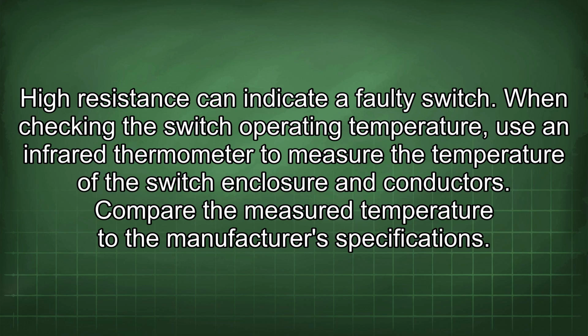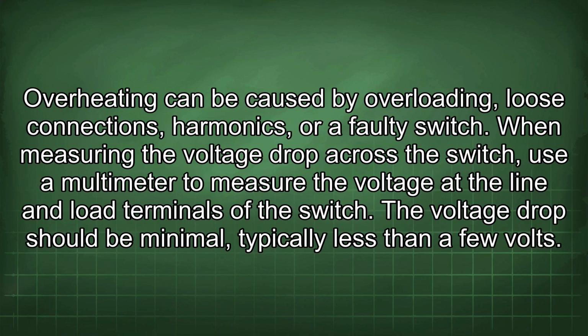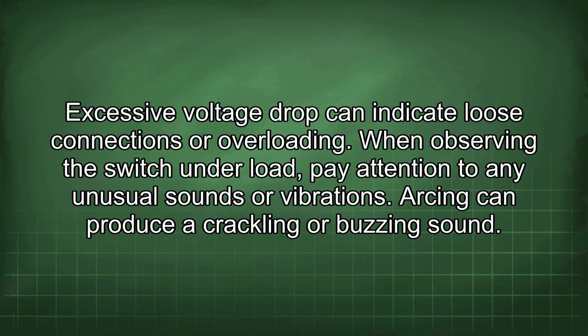When checking the switch operating temperature, use an infrared thermometer to measure the temperature of the switch enclosure and conductors. Compare the measured temperature to the manufacturer's specifications. Overheating can be caused by overloading, loose connections, harmonics, or a faulty switch. When measuring the voltage drop across the switch, use a multimeter to measure the voltage of the line and load terminals of the switch. The voltage drop should be minimal, typically less than a few volts. Excessive voltage drop can indicate loose connections or overloading.